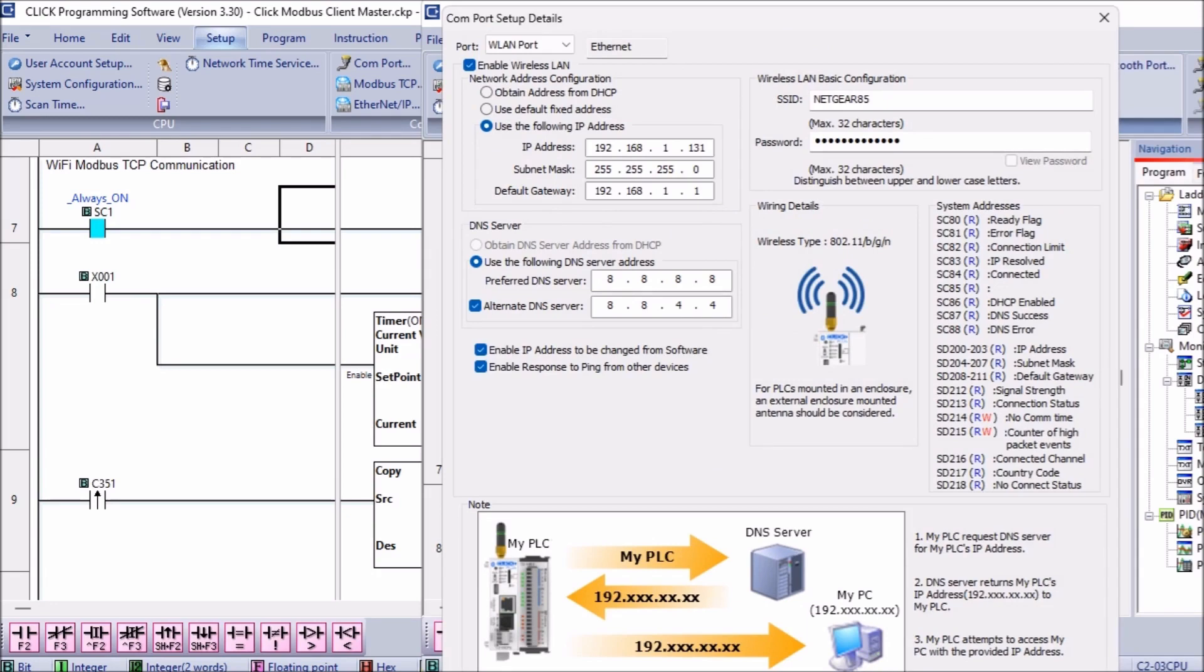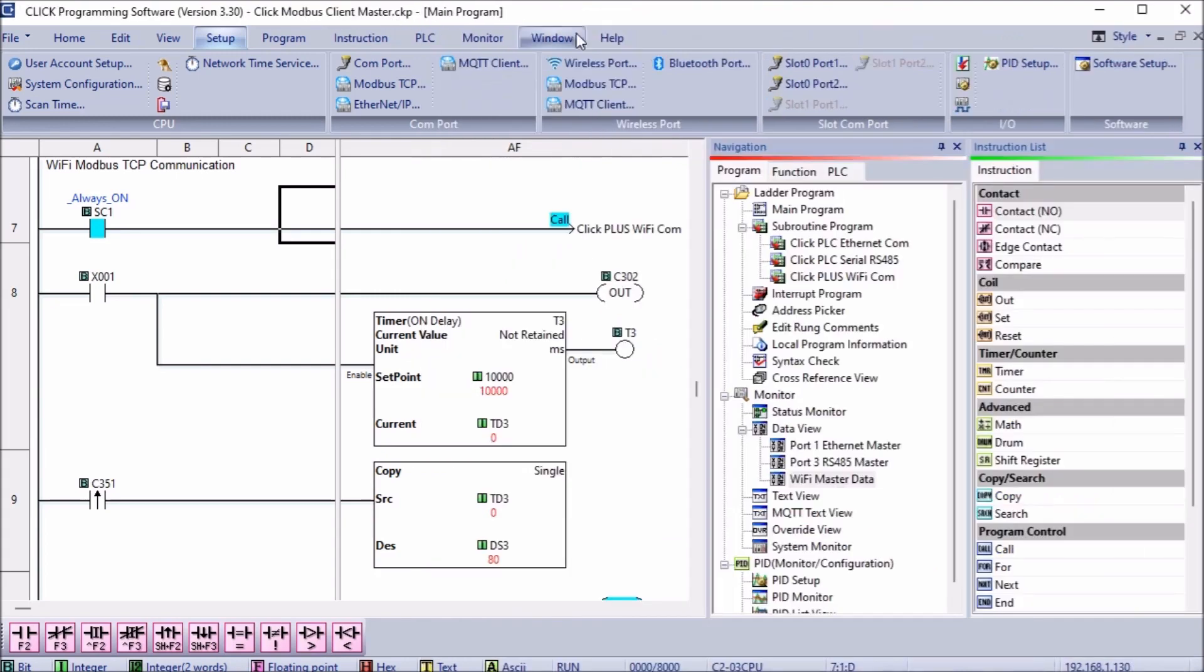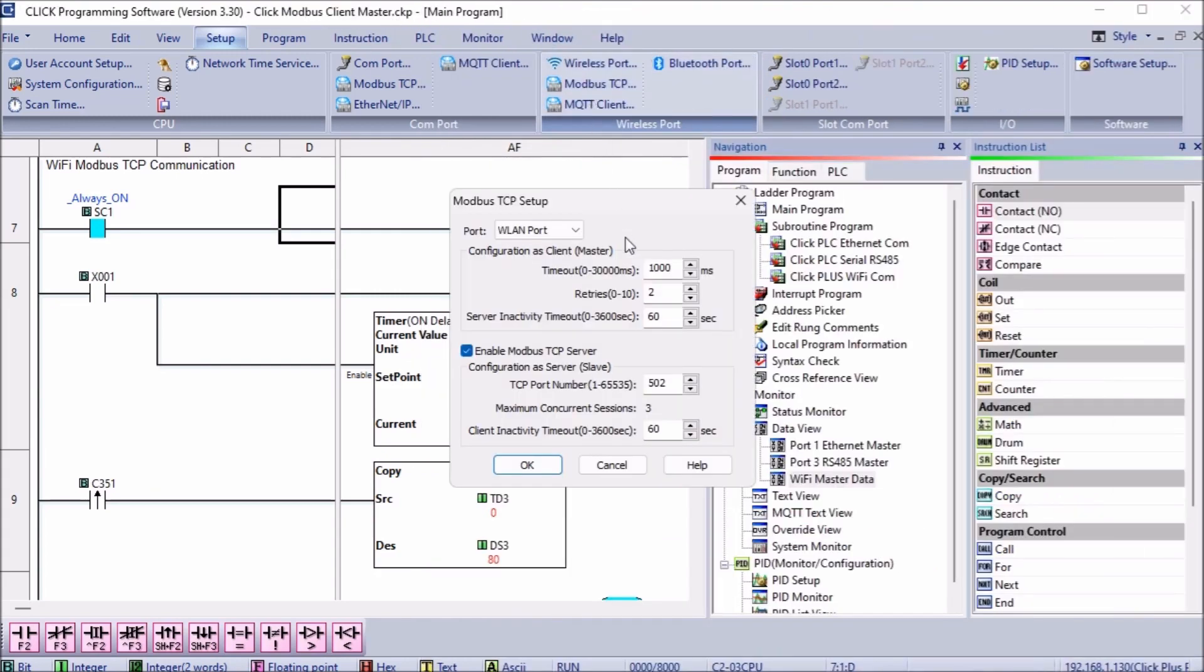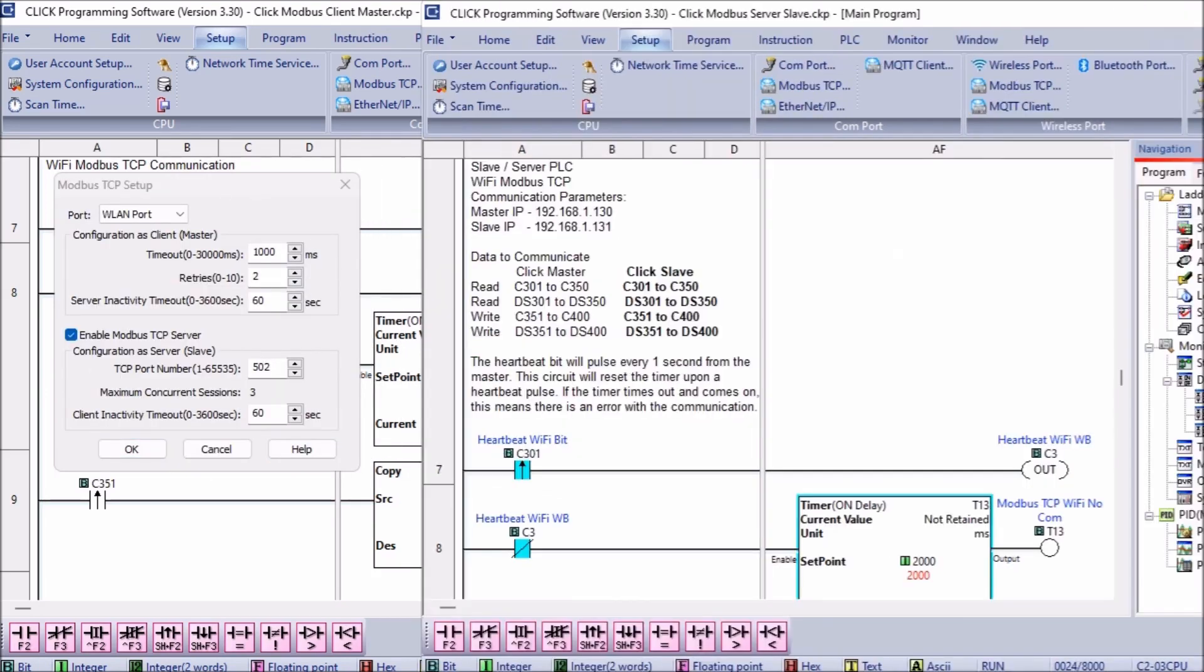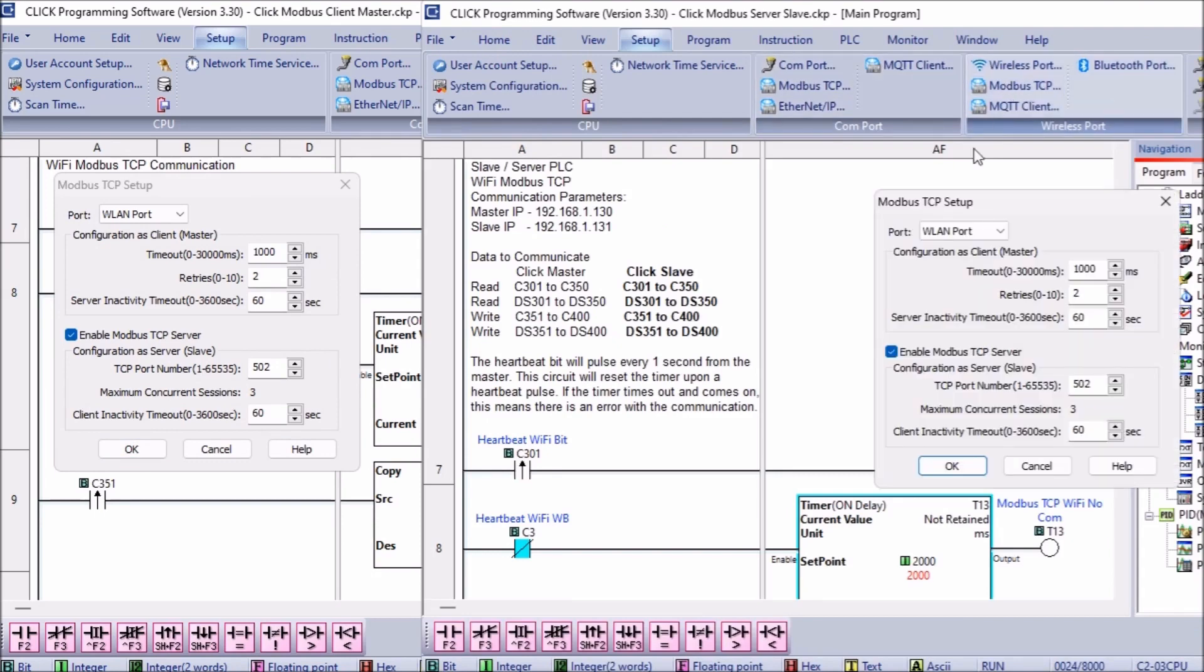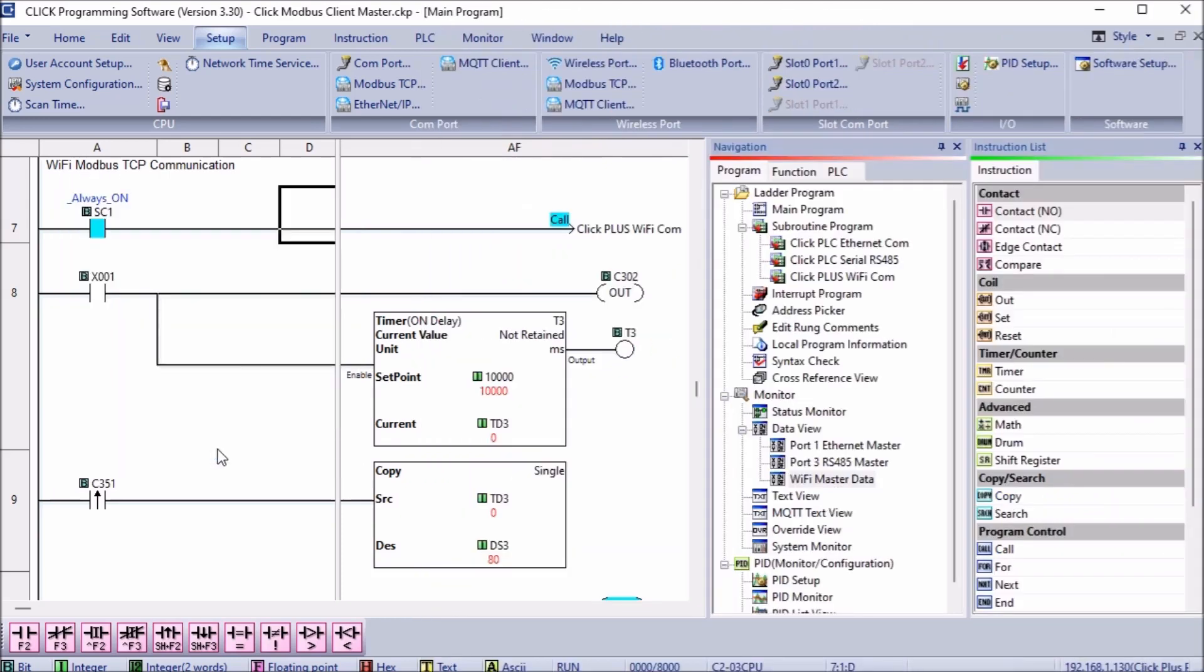The client Click PLC will use address 192.168.1.130 and the server Click PLC will use address 192.168.1.131. Select OK to return to the main screen. Under the Wireless Port selection in the setup menu, select Modbus TCP. This Modbus TCP setup window will allow us to set parameters around the protocol. We will leave the default settings for both the client and the server Click PLCs. Ensure that the enable the Modbus TCP server on the Click Remote IO PLC is selected. Our Click PLC network ports are now set up.